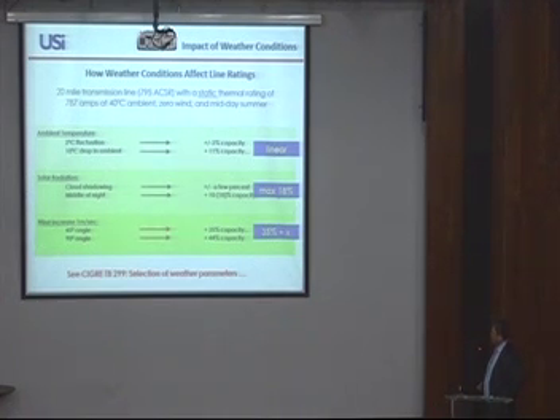But look at the wind speed and direction. If you take an angle of attack of 45 degrees of wind to the transmission line, and if you increase the wind speed by 1 meter per second, you will have 35% more transfer capacity on the line. And if it's perpendicular, you have 44%. So comparing these three ambient conditions, and this is known, the wind speed and angle has the biggest impact on the conductor temperature.